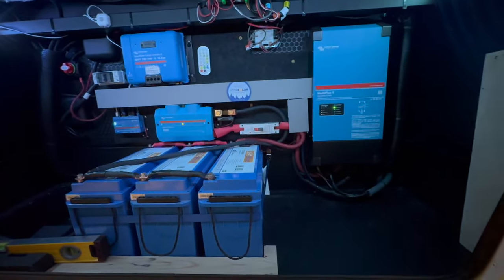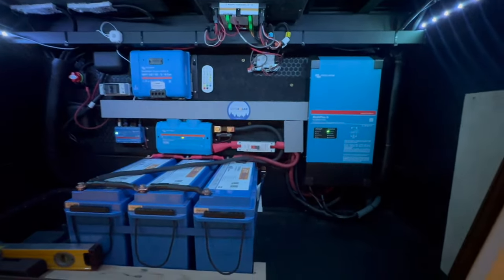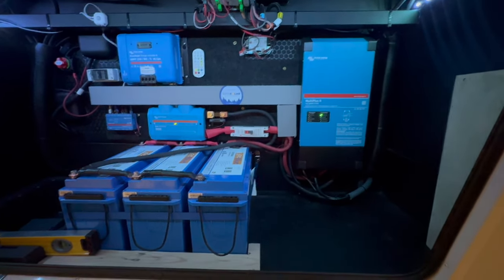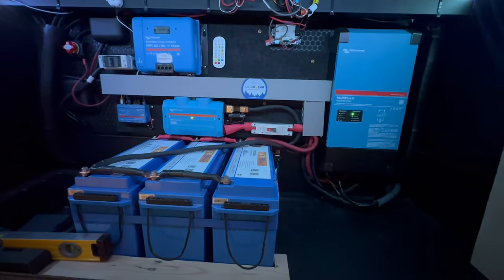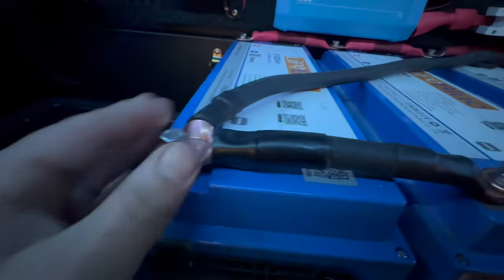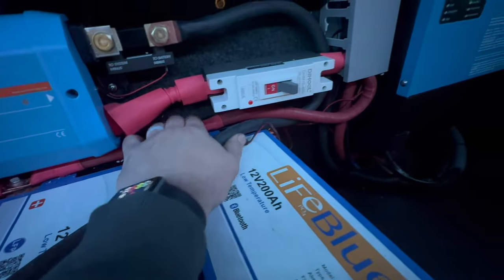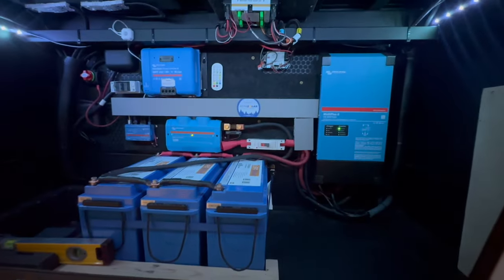If you're doing this, make sure you don't forget — it's easy. We've been running this for a while now and the connections are still staying cool. Are we still running 150 amps? Yes. This is probably about the hottest point right now and it doesn't feel bad at all. You could run that all day long, not a problem.